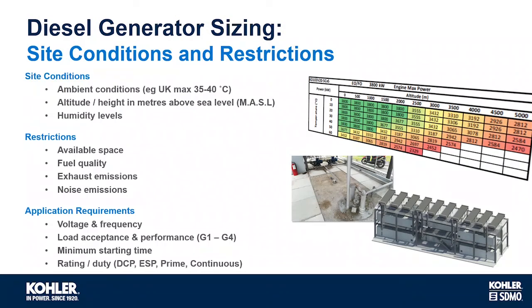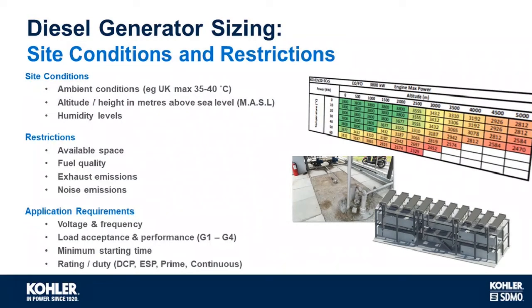So let's consider some of the site conditions and restrictions. Well, typically in the UK, our ambient is between 35 and 40 degrees, but other parts of the world may be much higher, as much as 55 degrees. Height above sea level is important because that affects the ability of the engine to produce power due to the reduced oxygen levels within the air. Humidity needs to be considered, although this does not normally affect the engine from a power delivery perspective.